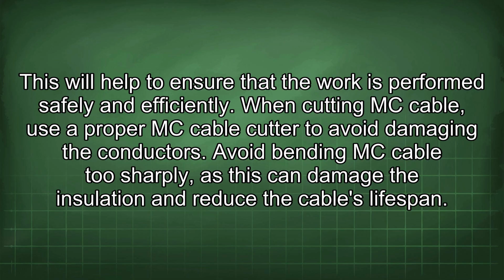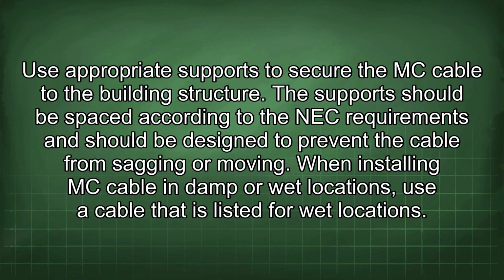When cutting MC cable, use a proper MC cable cutter to avoid damaging the conductors. Avoid bending MC cable too sharply, as this can damage the insulation and reduce the cable's lifespan. Use appropriate supports to secure the MC cable to the building structure. The support should be spaced according to the NEC requirements and should be designed to prevent the cable from sagging or moving.